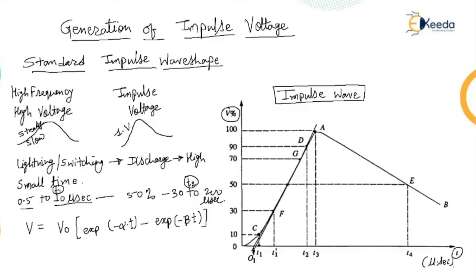The general waveshape is shown in the figure. The impulse waves are specified by defining their rise or front time, fall or tail time to 50% peak value, and the value of the peak voltage. The voltage is 1.2 by 50 microsecond. 1.2 to 50 microsecond, where this 1.2 indicates the rise time that is T1, and 50% drop of the voltage in 50 microseconds that is decay time or discharge time. Similar way here, the voltage rises in 1.2 microseconds and 50% of that voltage is reached in 50 microseconds. The peak value of the voltage is 1000 kV if we consider this kind.